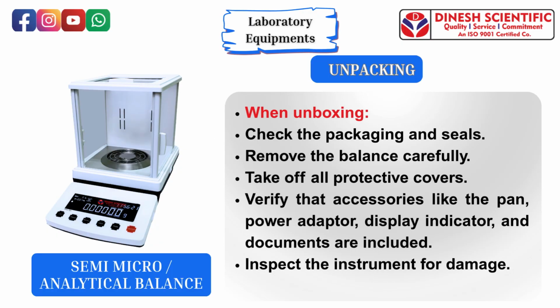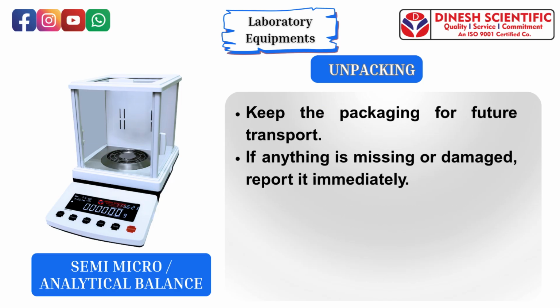Unpacking. When unboxing, check the packaging and seals. Remove the balance carefully. Take off all protective covers. Verify that accessories like the pan, power adapter, display indicator, and documents are included. Inspect the instrument for damage. Keep the packaging for future transport. If anything is missing or damaged, report it immediately.